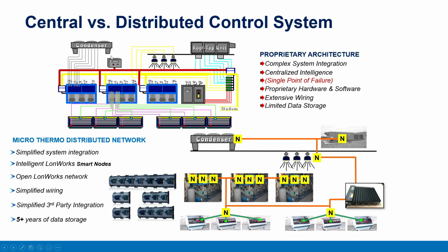Many other modalities, you may have one central store controller that has to make the decision for every device and board that's operating within the system. With Microthermo, we use what are called smart nodes, and we distribute the smart nodes throughout the facility: condenser, rooftop, lights, at the rack, in the cases, etc. And they are all tied together through a Windows 10, what we call an HMI, a human machine interface.